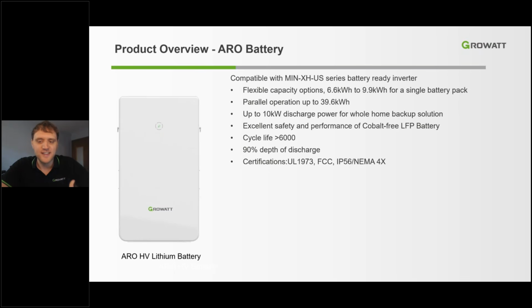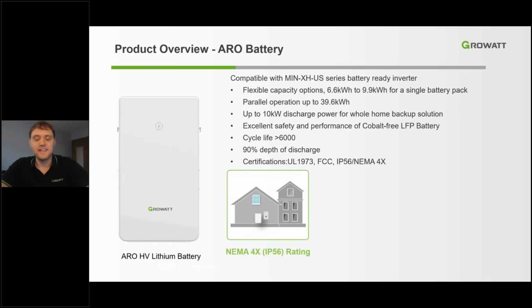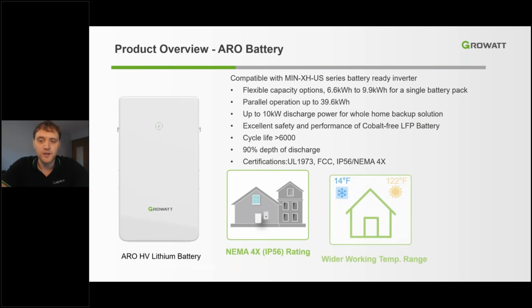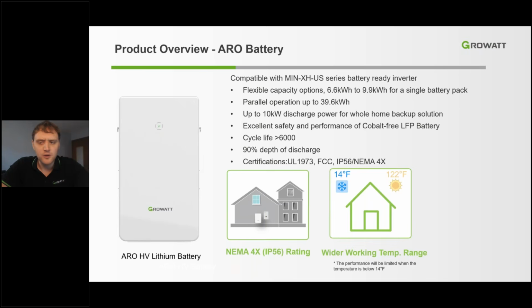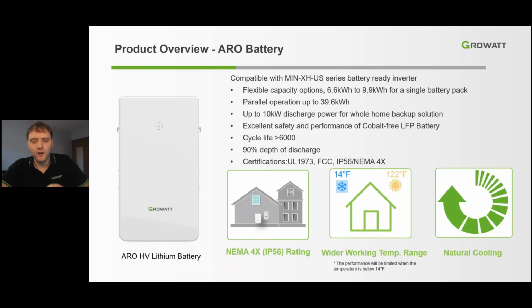The chemistry of the battery is that safe and reliable lithium iron phosphate with a cycle life of greater than 6,000 battery cycles. The ARO battery also features a very impressive 90% depth of discharge for greater use of the battery capacity. Battery is NEMA 4X rated, features a wide working temperature range from 14 to 122 degrees Fahrenheit, and is quietly cooled through convection. When paired with the MIN inverter, your entire system warranty is covered by one manufacturer to eliminate that confusion of dealing with multiple warranty periods, tech support agencies, and manufacturers alike.